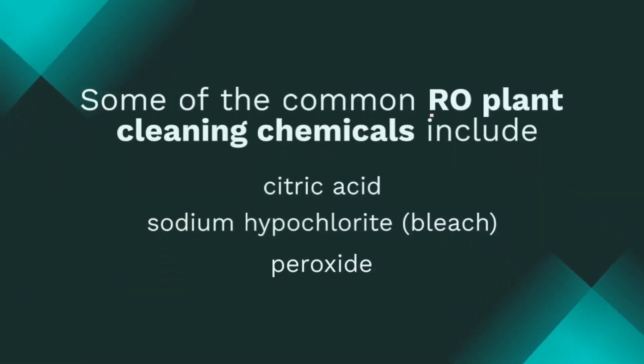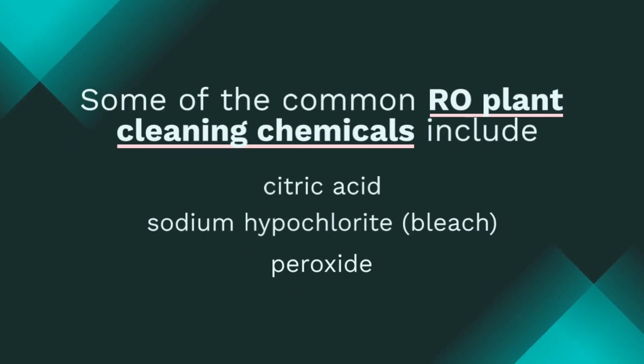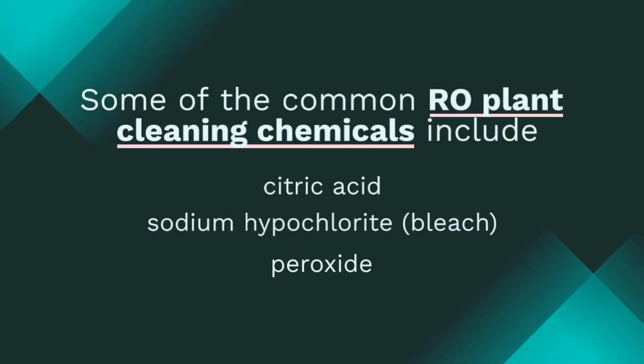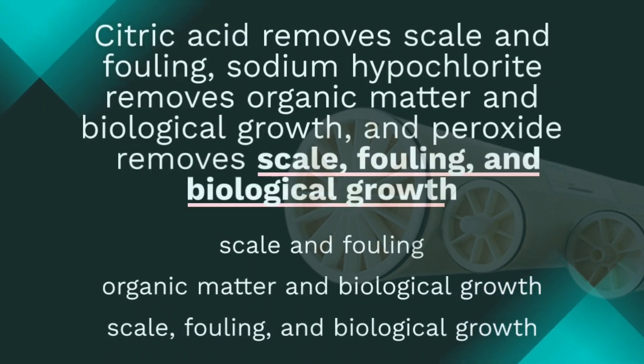Question 3: What are some of the common RO plant cleaning chemicals? Some of the common RO plant cleaning chemicals include citric acid, which is a weak acid used to remove scale and fouling from RO membranes, and sodium hypochlorite, a strong oxidizer used to remove organic matter and biological growth from RO membranes.